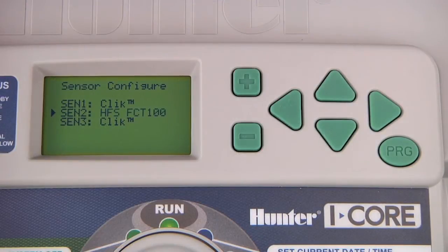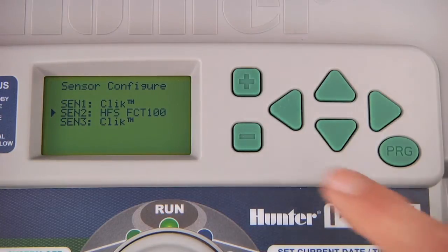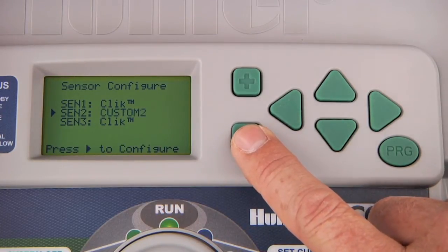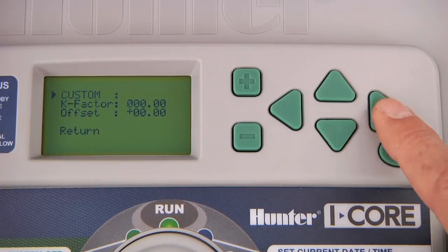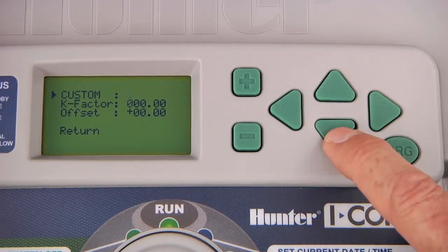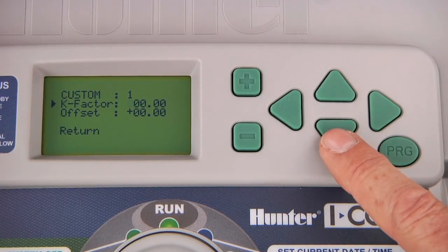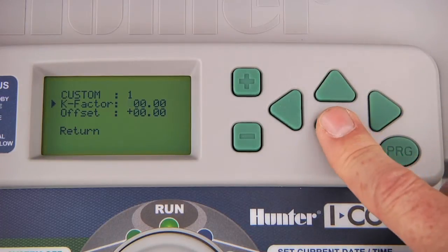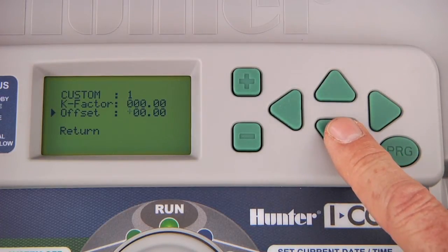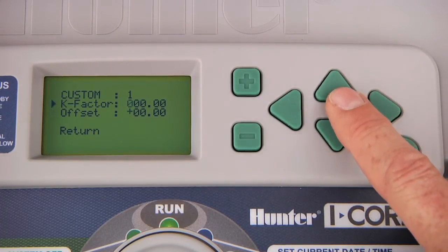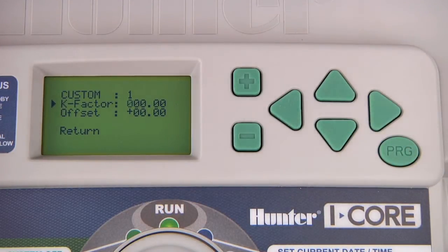On the other hand, if you are using a non-Hunter flow sensor, choose Custom 1, press the right arrow button to configure it by entering the K factor and the offset specified by the manufacturer of your particular flow sensor. The Custom 2 and Custom 3 settings are not normally used, but can be used if you choose to use multiple flow inputs with different sized meters. Keep in mind there is only one master valve output, but it is possible to connect a flow meter to each sensor input in the I-Core.